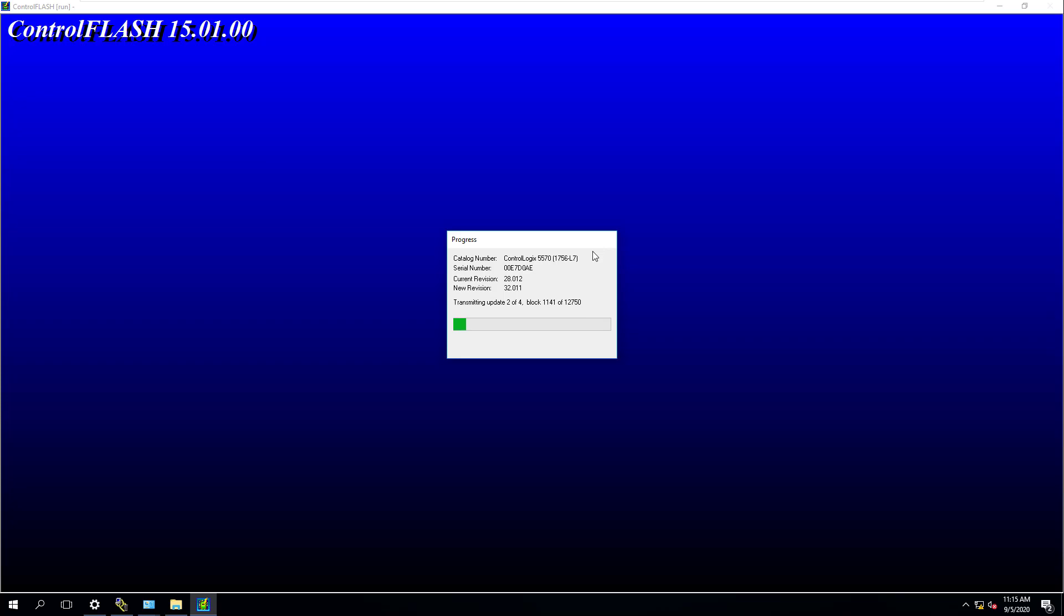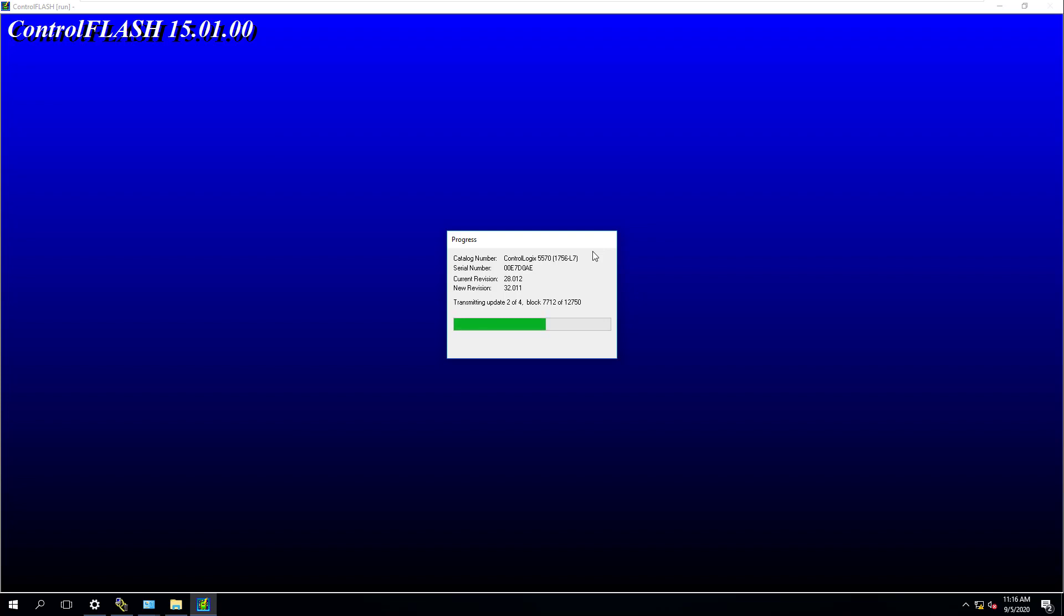Again, we've talked about this, and I'm going to put this back in here, I'm going to come in here, put that in there, then I'm going to select this. This is going to actually pop up the new process where I can actually take it to version 32, right? So now I can take it to version 32, and then we can actually flash it to version 32. Now this is again, it doesn't, it has to be an L7 or greater. So it has to be L7 or greater. It's going to give you a couple things for basically indications of like digital cards and stuff like that if you haven't installed. But just note that when you're flashing this stuff, you just know when to use the right file. Now I know there's some questions right here that may come up, where am I going to get this, where am I going to get the firmware file, right? Well you have to get all the firmware from rockwellautomation.com or ab.com. Again, that's where you get the firmware, and I'm pretty sure you have to have an account. If you don't have an account, it's free to sign up. If you have an account, you can get the firmware.